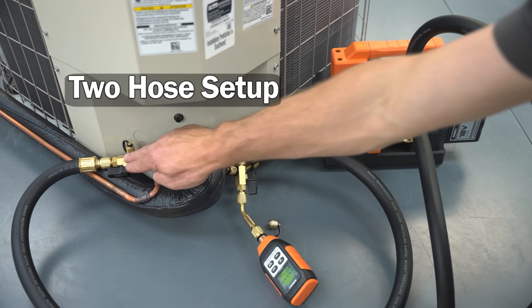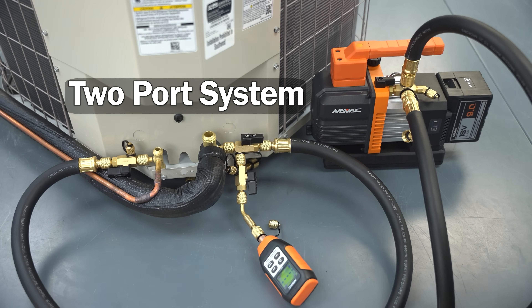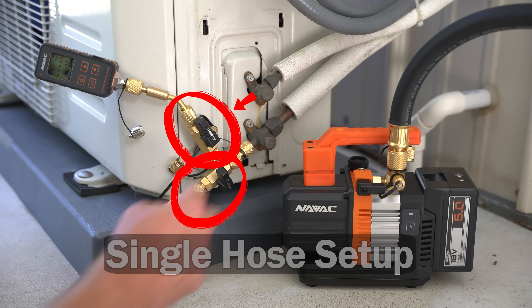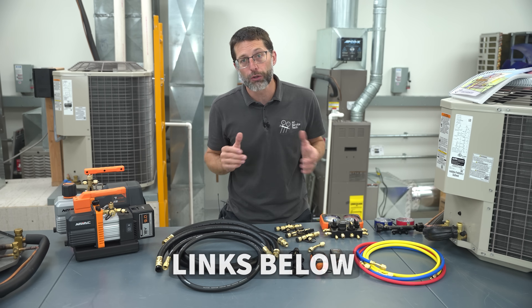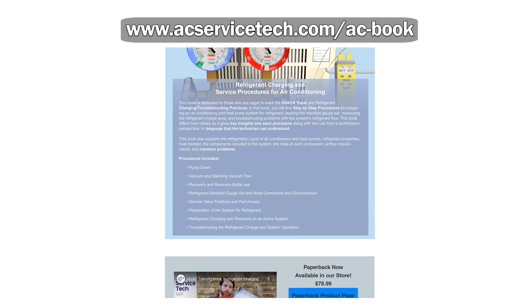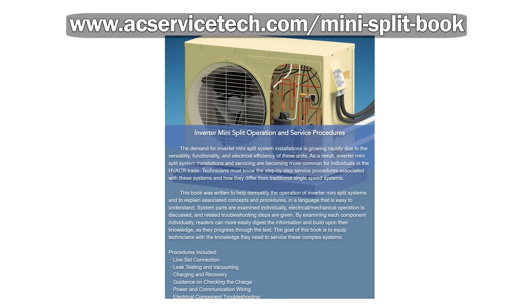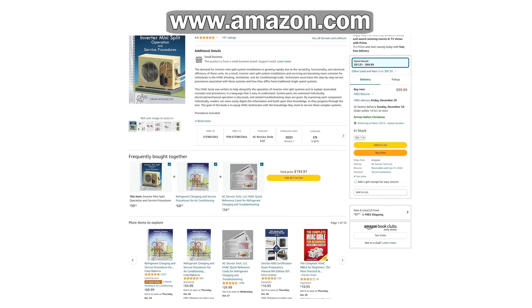In summary, I highly recommend using a two-hose vacuum setup with three valve core removal tools to pull an effective vacuum on a two-port system. For a single-port system such as a mini-split, use a single-hose setup with two VCRTs — the second one to valve off the vacuum gauge when breaking the vacuum with refrigerant. Tools used in this video are linked in the description below. For more on HVAC, check out the Refrigerant Charging and Service Procedures for Air Conditioning book and the Inverter Mini-Split Operations and Service Procedures book at acservicetech.com or on Amazon.